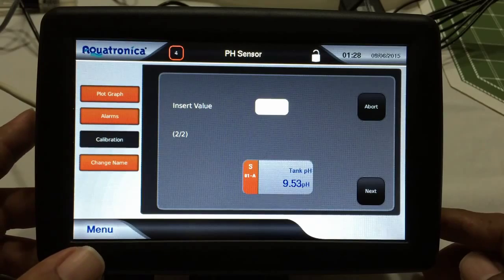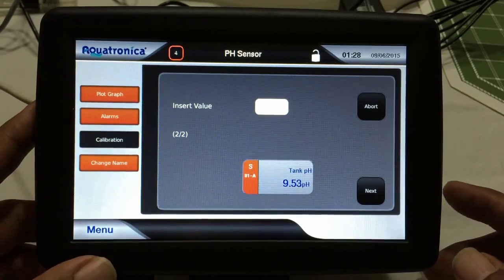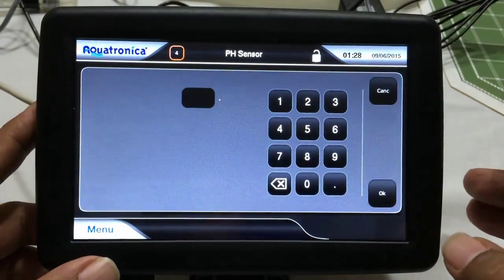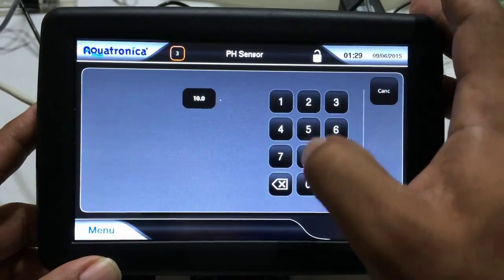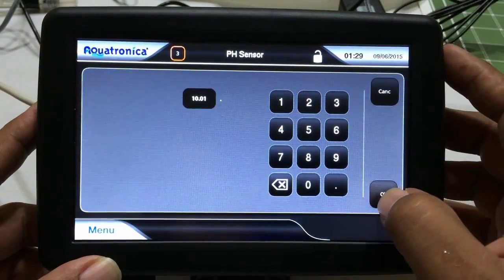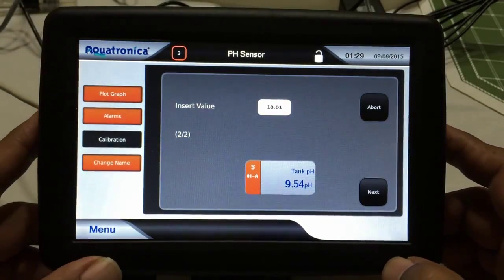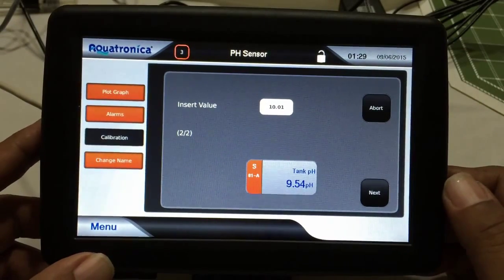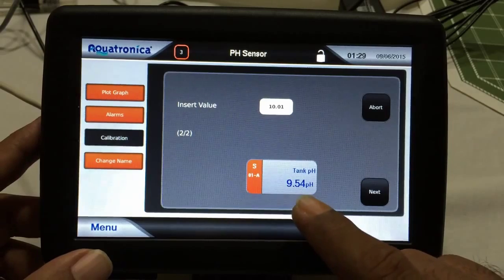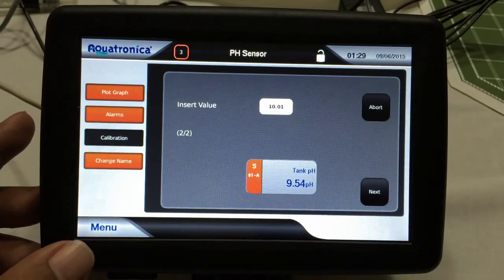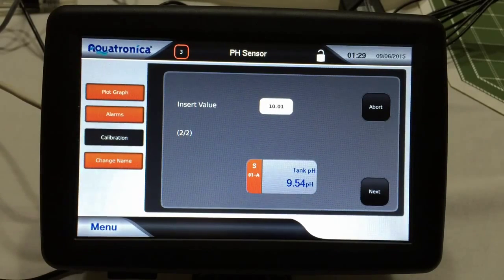It's going to take a little bit of time to stabilize, but in the meantime I can put in the value, which is 10.01. So I'm going to put in 10.01, press OK, and don't hit next yet. Wait until this value stabilizes, and typically, in most cases, that'll take a couple minutes to stabilize, 5-10 minutes.